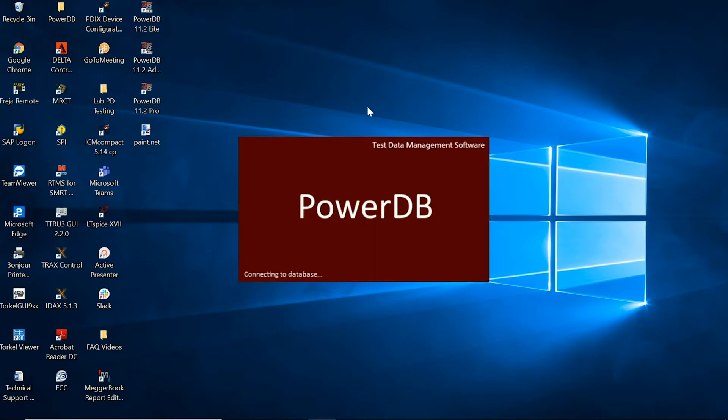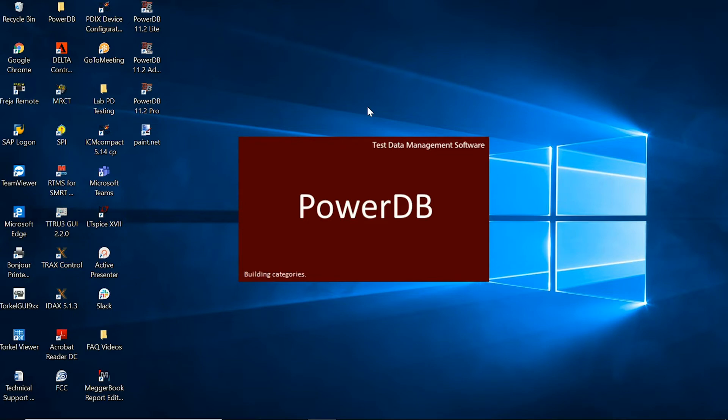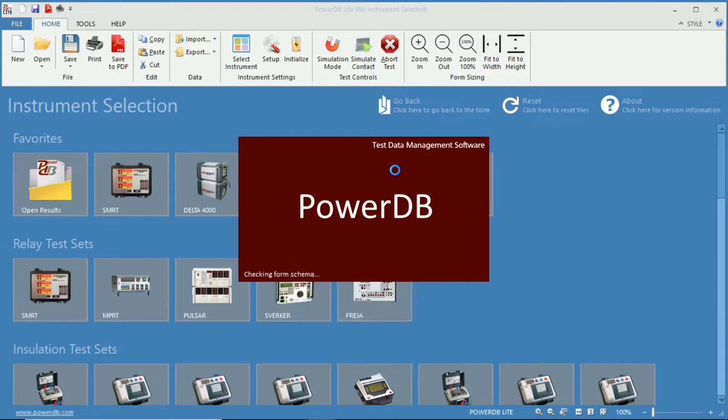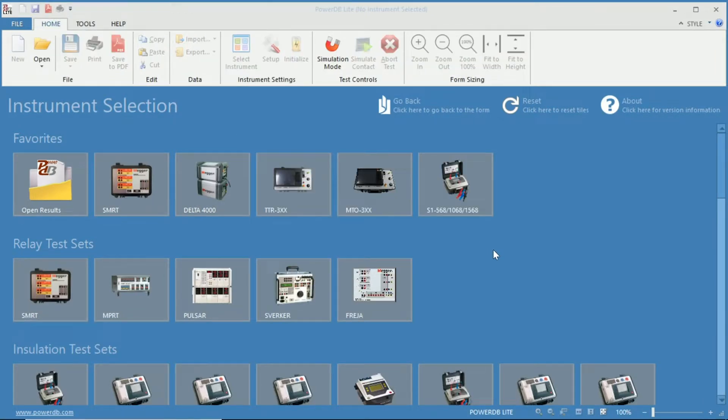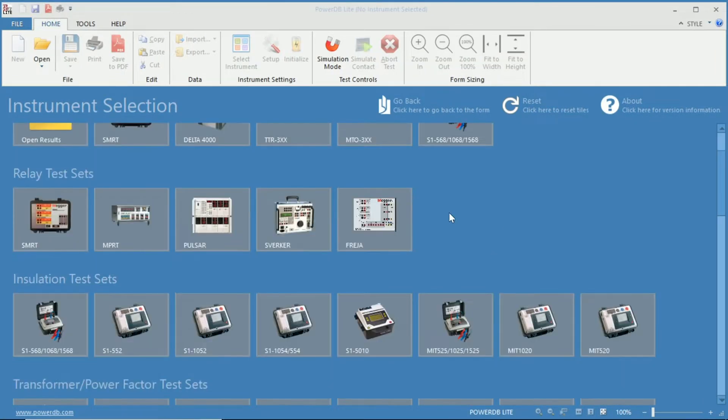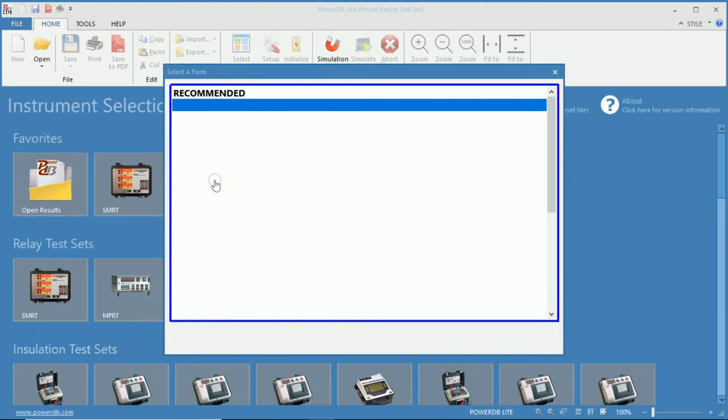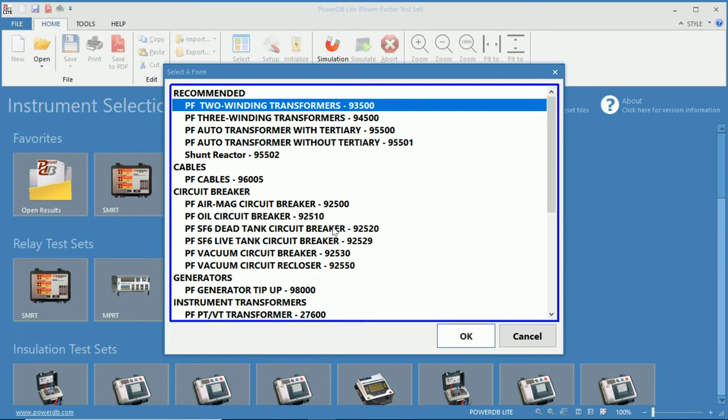In this case that's PowerDB Lite version 11.2.9. Once the software is open you can see the list of instruments. We'll be choosing the Delta 4000 power factor test set using the power factor two-winding transformer 93500 test form.